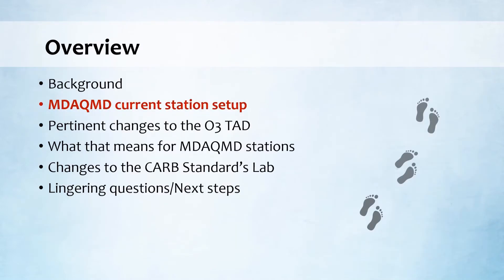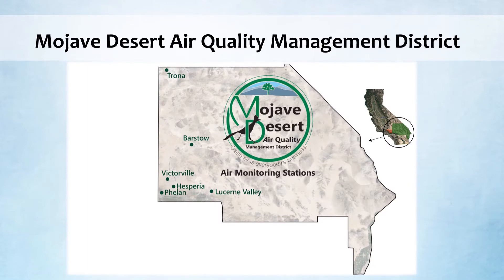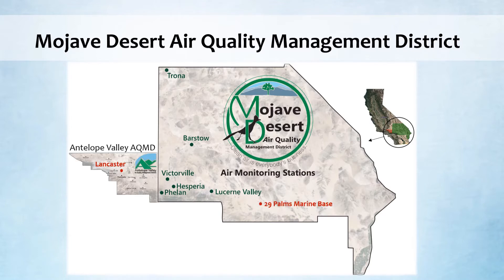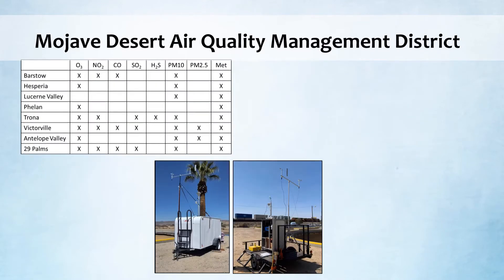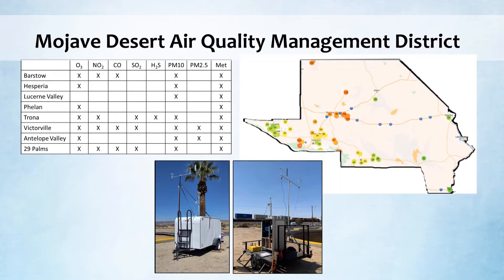That brings me to my next topic: the Mojave Desert AQMD current station setup. I work for the Mojave Desert Air Quality Management District. We are the second largest district in the state at just under 20,000 square miles. We run six regulatory stations plus two contract stations — one for the Antelope Valley AQMD, which is a regulatory site, and one at the 29 Palms Marine Base, which is not a regulatory site. Across these eight sites, we measure all of the criteria gases plus H2S, continuous PM10 and PM2.5, and MET, making a total of six regulatory ozone analyzers plus the one at 29 Palms. We also have two stations for mobile smoke monitoring and have deployed around 50 PurpleAir sensors across the two districts. We have three techs to keep all this going, so we stay pretty busy.